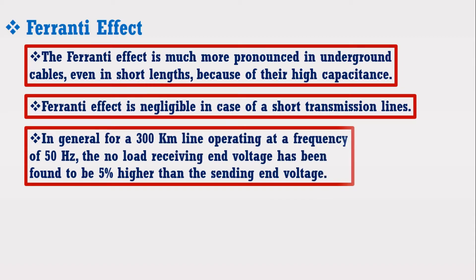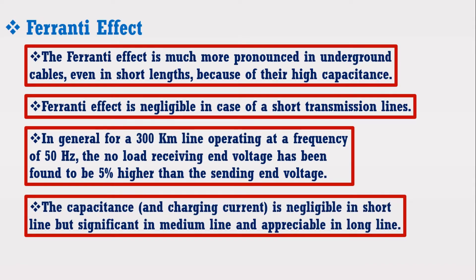Ferranti effect is negligible in case of a short transmission line. For a 300 km line operating at a frequency of 50 Hz, the no-load receiving end voltage has been found to be 5% higher than the sending end voltage. The capacitance is negligible in short lines but significant in medium lines and appreciable in long lines. Therefore, this phenomena occurs in medium and long lines.